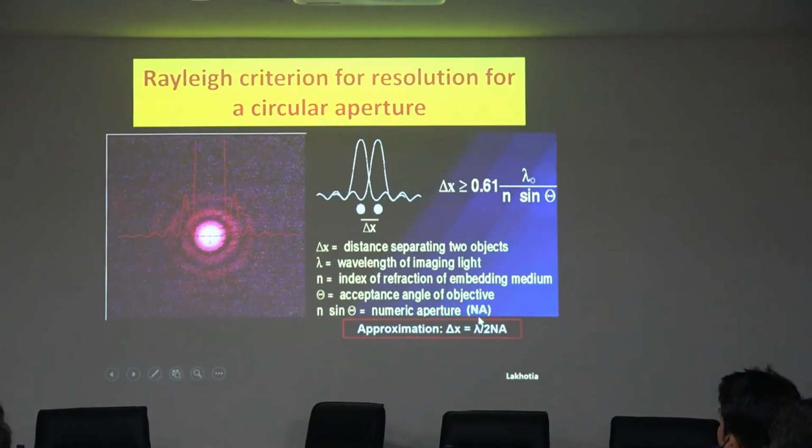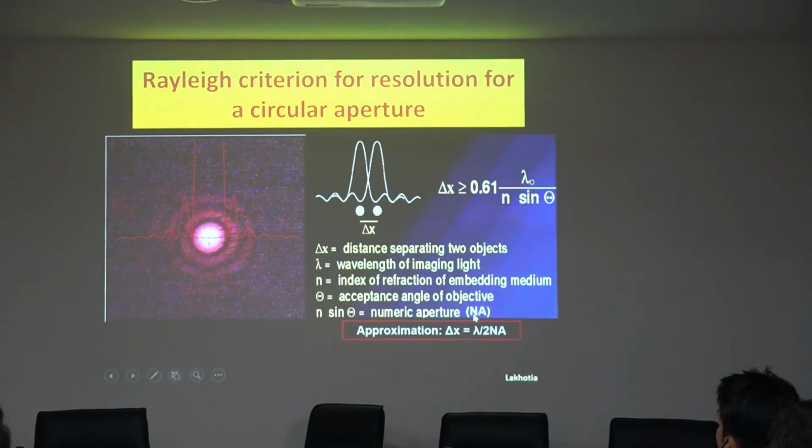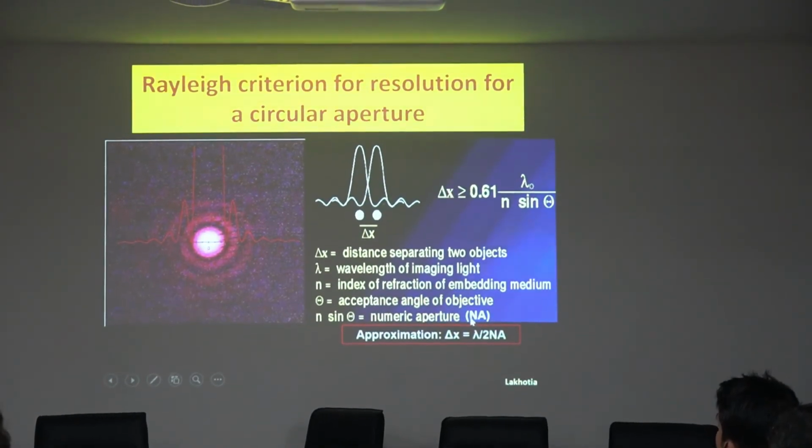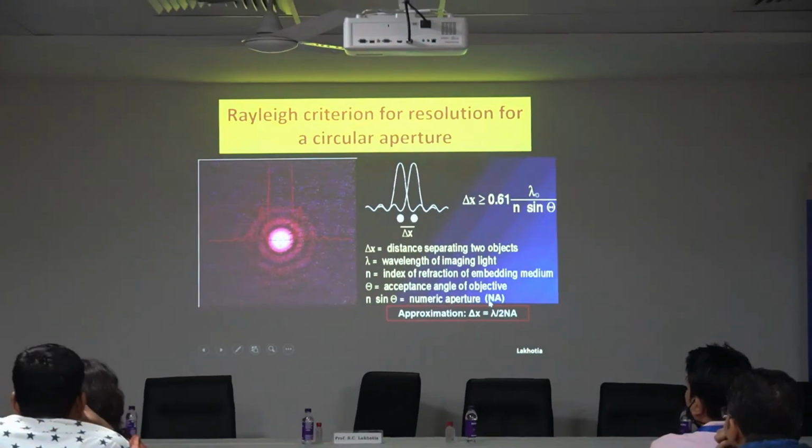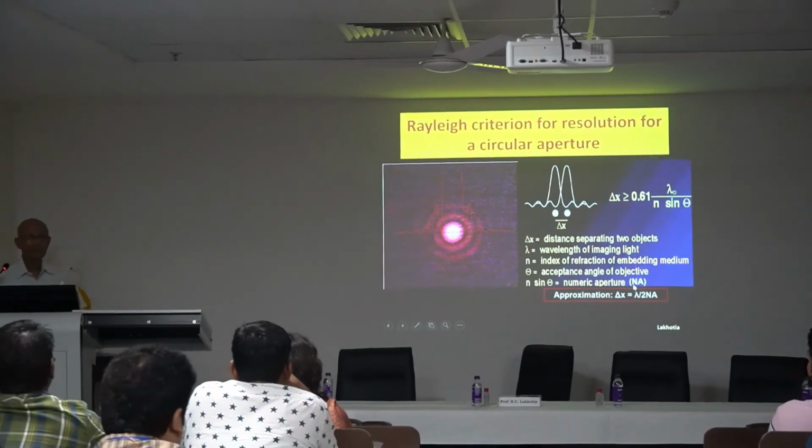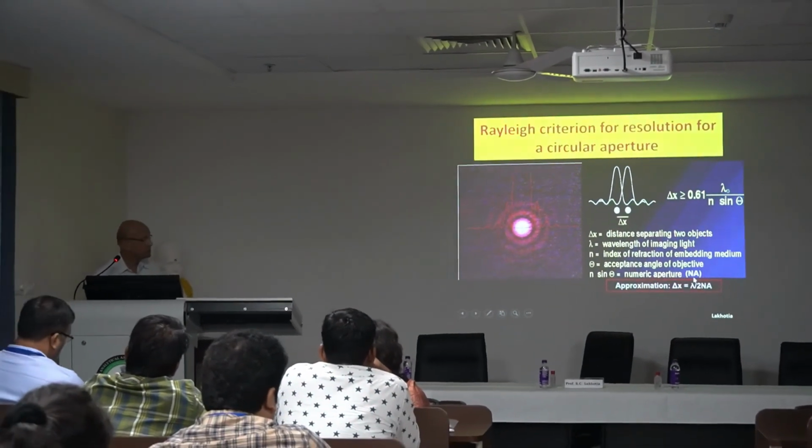But that value is operational, functional, or useful only when the illumination system is properly adjusted. If you don't adjust the illumination system, NA has no meaning, and you won't be able to resolve.